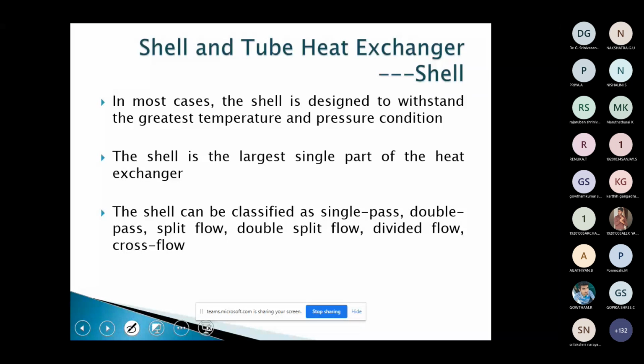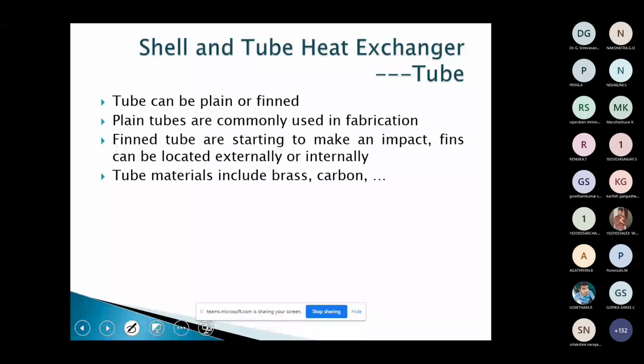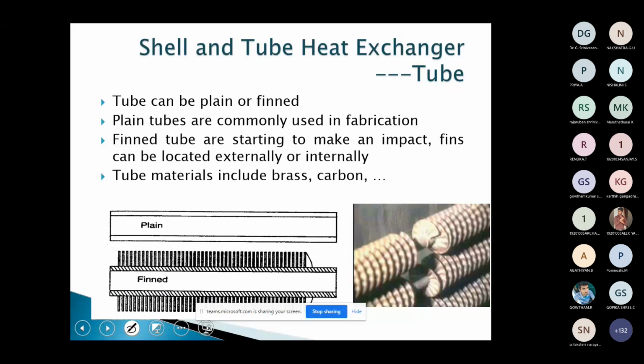As we saw earlier, the shell side can be classified into single pass, double pass, split flow, double split flow, divided flow, cross flow, etc. Right, coming to the tube side. These tubes may be plain or finned. Plain tubes or finned tubes are used to enhance the heat transfer. That is why fins are used. Normally, we use plain types. You can see these are all plain type tubes, and this is the finned type. You can see the diagram here. This is done to increase the rate of heat transfer in certain cases. But with fins, cleaning is highly difficult. That is one of the important things.